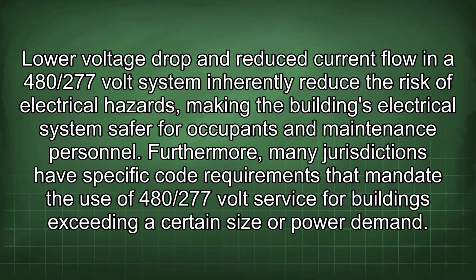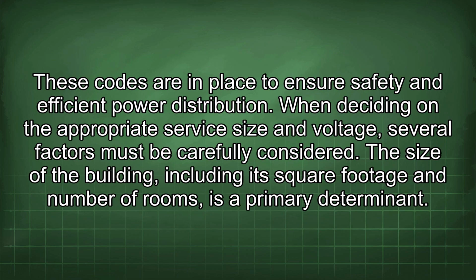Furthermore, many jurisdictions have specific code requirements that mandate the use of 480/277 volt service for buildings exceeding a certain size or power demand. These codes are in place to ensure safety and efficient power distribution. When deciding on the appropriate service size and voltage, several factors must be carefully considered. The size of the building, including its square footage and number of rooms, is a primary determinant.